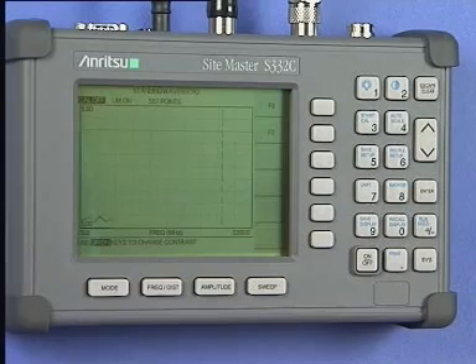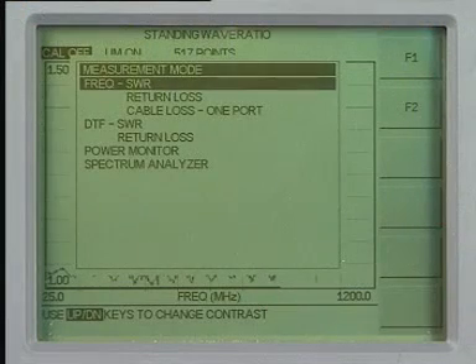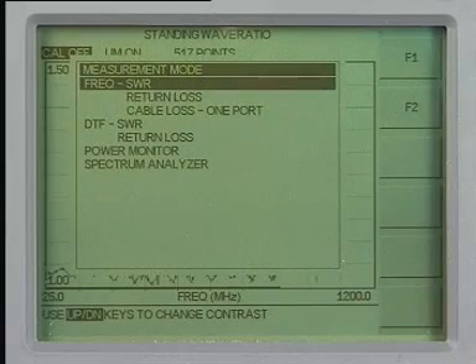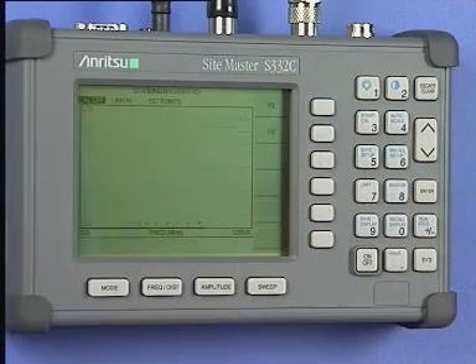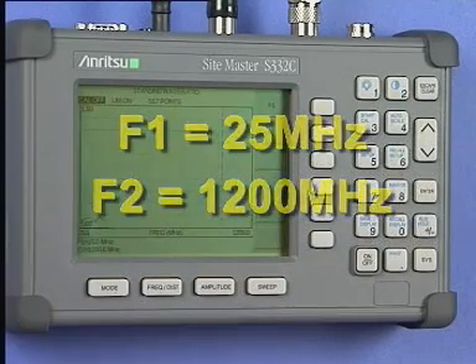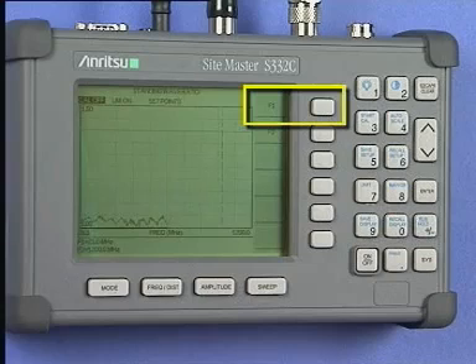Now continue by telling the Site Master what range of frequencies you will be using. Press the Mode key, then use the Up-Down key to select Frequency SWR in the screen menu. Press the Enter key to select this option. On this CD-ROM we will be using 25 MHz and 1200 MHz for all examples, even in the interactive presentations. Press the Frequency Distance key, then press the F1 soft key to select the lower frequency limit. Enter the lower frequency limit, which in our presentation is 25 MHz.